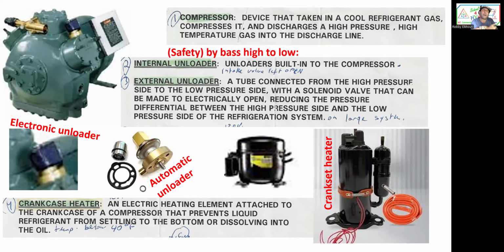Then we have the crankcase heater. It's a little heater that goes around the compressor in the off cycle to keep the oil from, it's called fractionation. It's part of the chemistry. I'll cover it when I do the Freon and oil class. And fractionation is also very important in HVAC. It's not a problem here in Florida, because the temperature never gets below 50 degrees. So I don't think you even need crankcase heaters here. We don't even need HPR valves here. I mean, Headmaster, cover later.